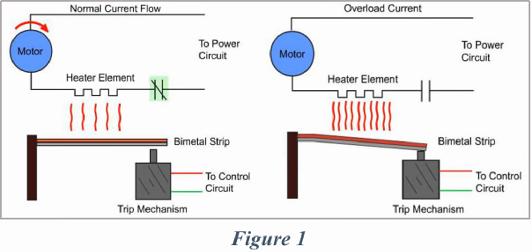Advantages of thermal overload relay. More convenient with efficient operating principle which results in high accuracy and protection to connected load. Suitable to use with single and three-phase electrical motors to protect from internal phase losses. Cost-effective and easy to install by using rail adapters. Available with internal trip level selection and internal testing switch for troubleshooting. Available in manual and automatic reset functions for convenient operations. Salient features of modifiable current range and temperature compensation for precise functioning.